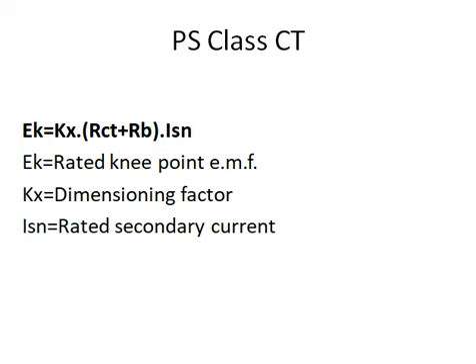For PS class CT, Ek is the rated knee point EMF, which will be defined in the technical particulars by the CT manufacturer. The formula is: Ek must be greater than or equal to (Rct plus Rb) multiplied by I_SN, where Rct is the CT secondary winding resistance at 20 degrees centigrade, Rb is the relay burden, and I_SN is the rated CT secondary current. If this equation is fulfilled, the CT selection is OK.